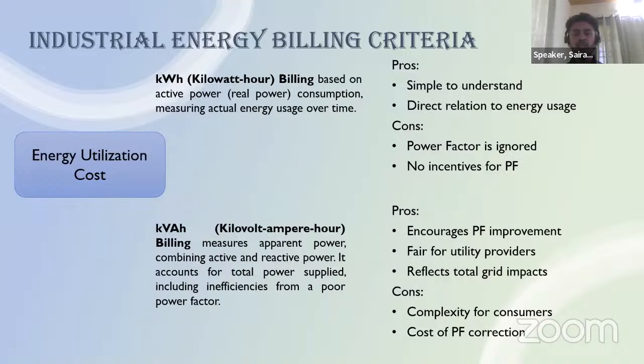In kVAH billing, they consider both powers, active and reactive power. It also relates to the power factor. If you maintain the power factor in a very poor way, then even if you consume lower real power, the kVAH will be increased in the ratio of that power factor. So the kVAH will be quoted as high. The benefit of kVAH billing on the industrial side is that it encourages power factor management. It insists that industries maintain the power factor. And it is also good for the utility providers.